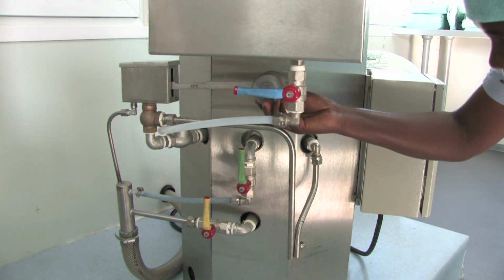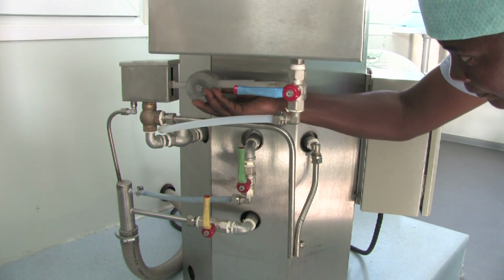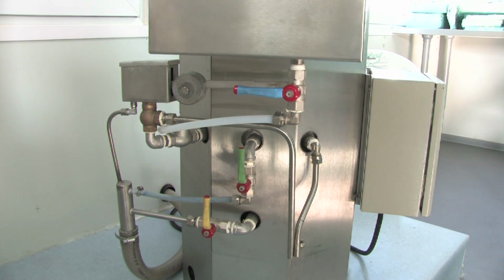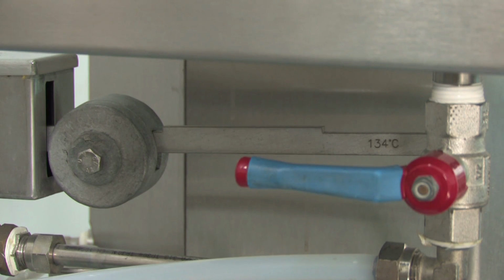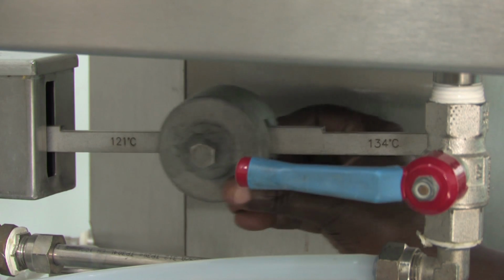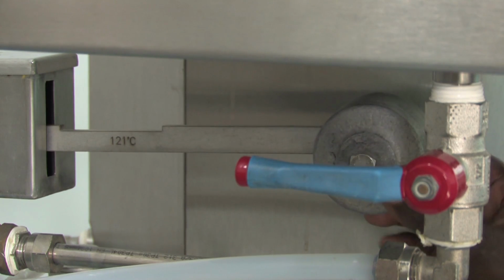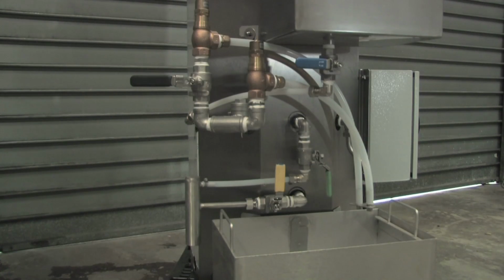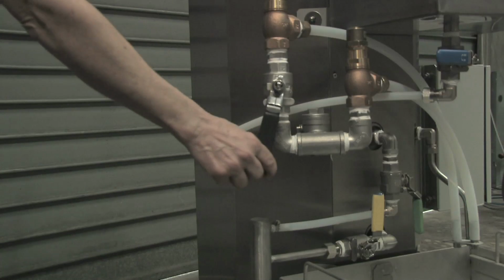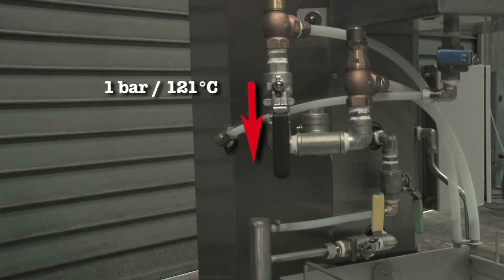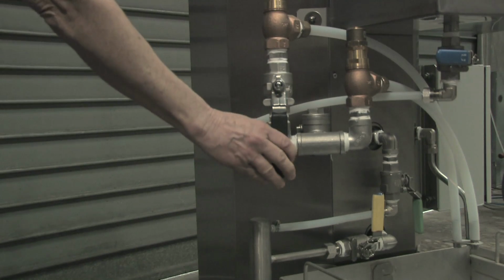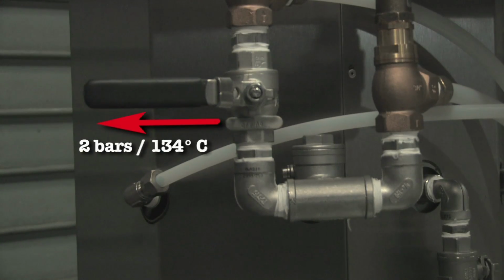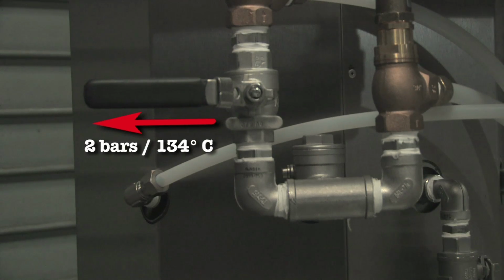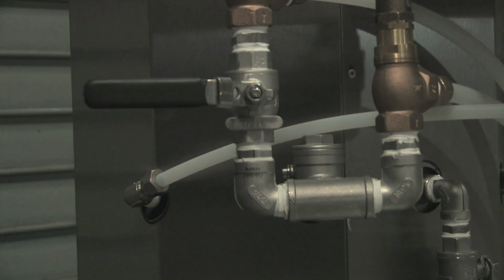The position of a counterweight along a metal bar determines the cycle temperature, either 134 degrees Celsius or 121 degrees Celsius, via its action on the pressure regulator valve. On newer models, the cycle is selected by opening or closing a black valve. When the valve is open, the steam pressure is 1 bar, and thus the temperature is 121 degrees Celsius. When the black valve is closed, the steam pressure is 2 bars, and the temperature is 134 degrees Celsius.